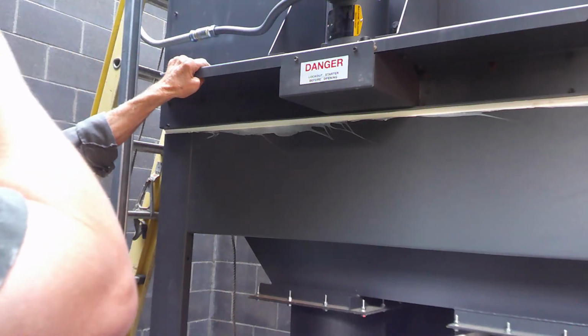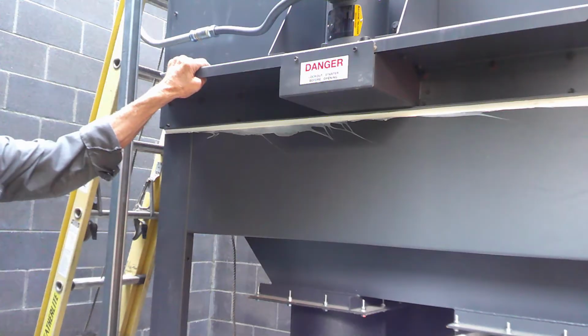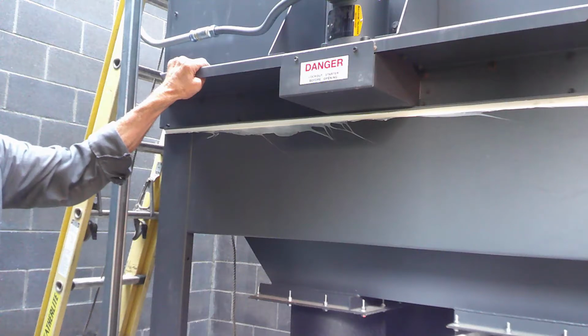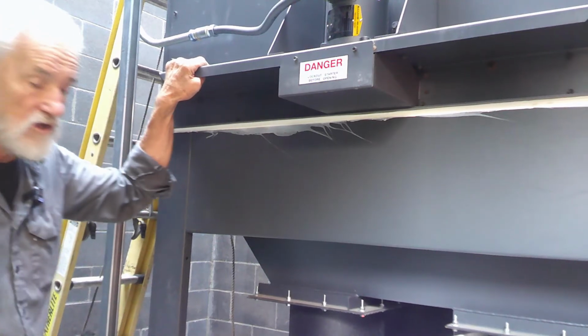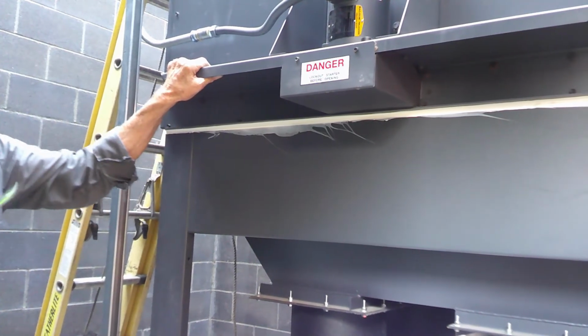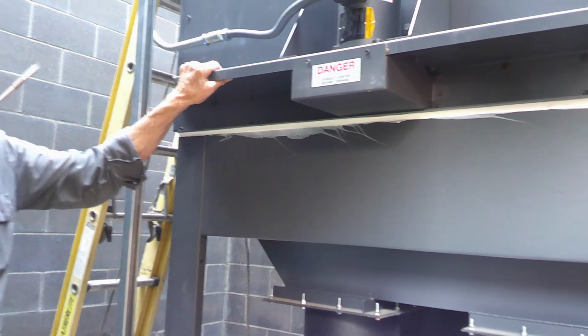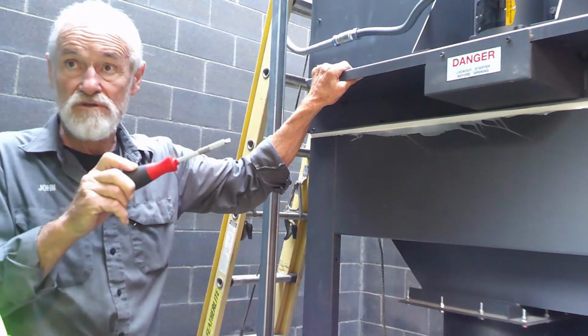Is that a manual thing, or does it do it all the time? It's a good question. Every time this unit is shut down, there's a time delay. The delay is built into the VFD so it knows when to stop running, because if it keeps running it'll suck the dirt right back up into the filters.